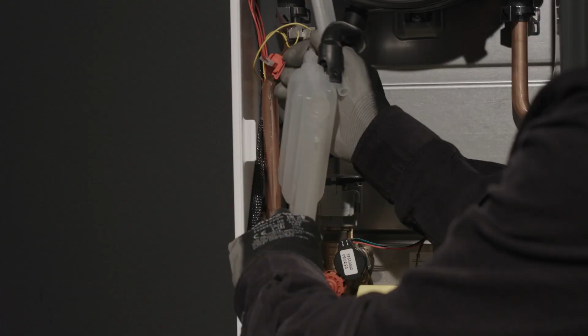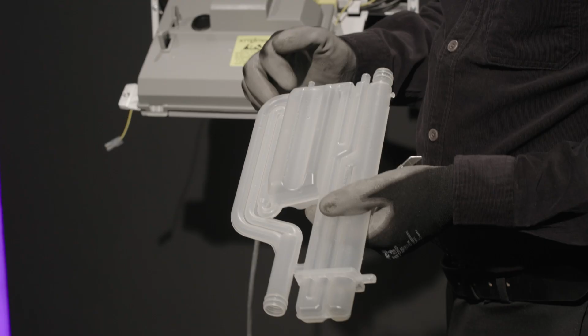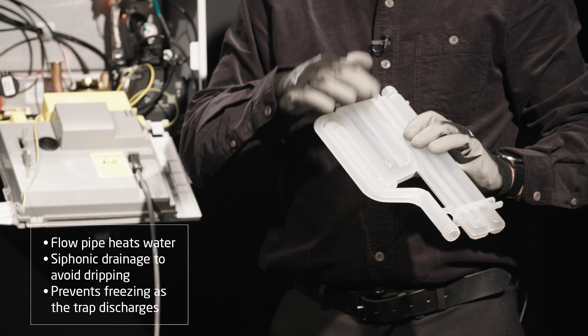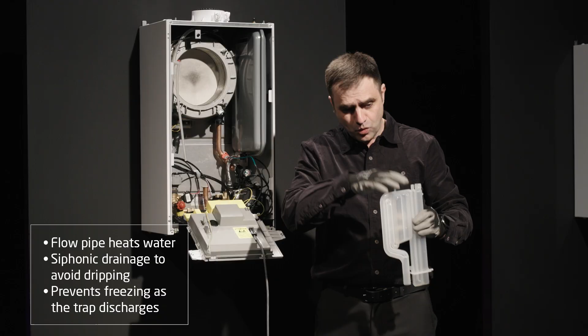So I undo the screw, and then I can lift out the retaining bracket, and the condensate trap can quite simply lift out as well. So remove the condensate trap, and as you can see it's got a groove here, and that's where the flow pipe sits, just in here. And that flow pipe obviously gets warm, and it heats up all that water that's in the condensate trap. And what that means is when it is released, all the water, because it is siphonic, it's not going to drip out, it's going to release it all in one go, it's warm, and there's far less chance of it freezing in cold weather. So that's a really good feature on there.